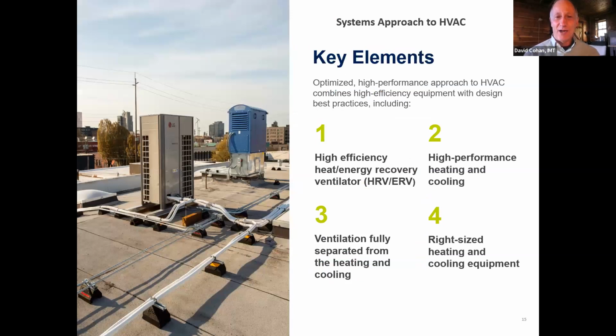So what are we actually talking about here? There are four key elements. One, you use really high efficiency heat or energy recovery. That's key. You use high performance heating and cooling. You fully separate the heating and cooling from the ventilation. And you right size these systems—you're not just going to replace what's on the roof. Typically we've been reducing systems by 30 to 50% in tonnage.